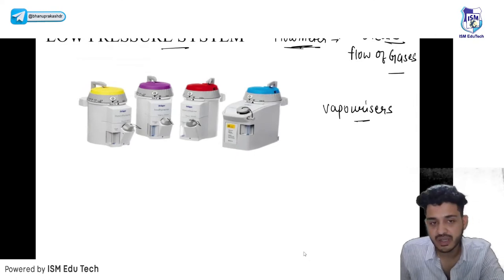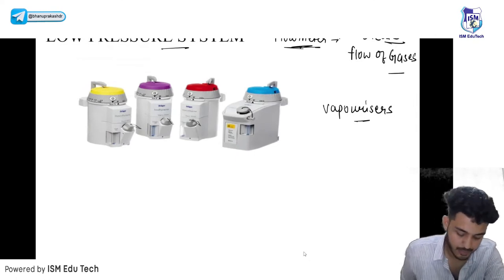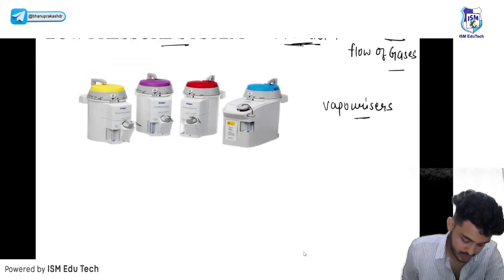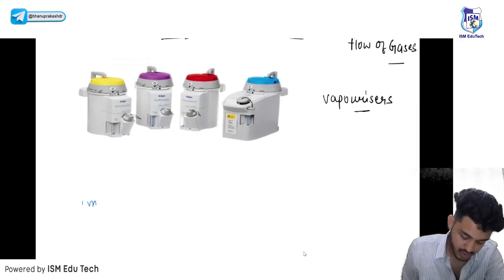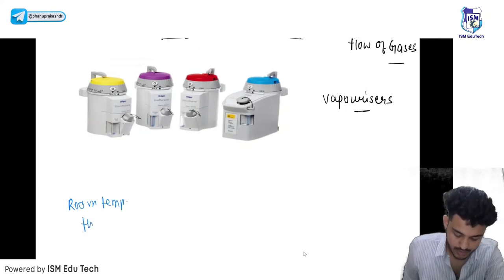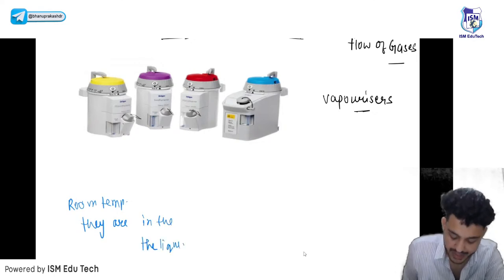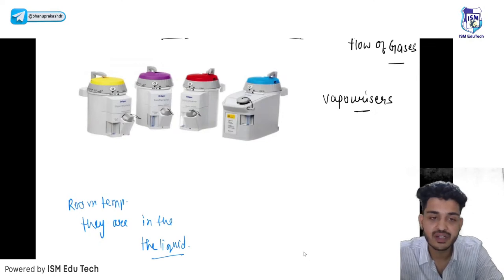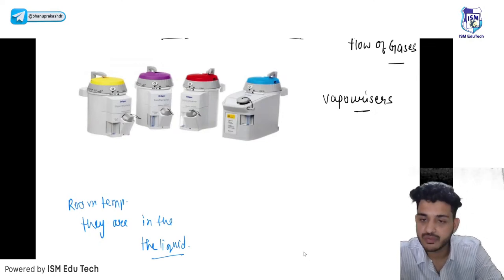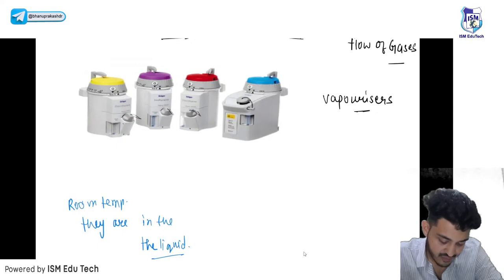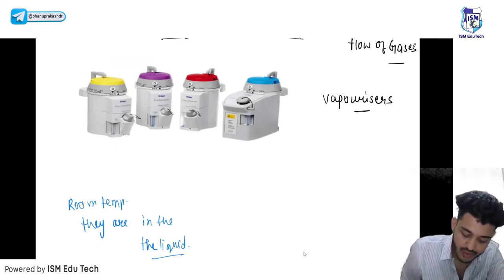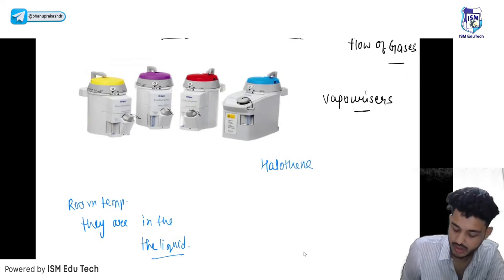Why do we need vaporizers? We need vaporizers because at room temperature, anesthetic agents are in the form of liquid, so we need to boil them up with the help of vaporizers. So we are having different kinds of vaporizers. You can remember halothane, we are having halo.